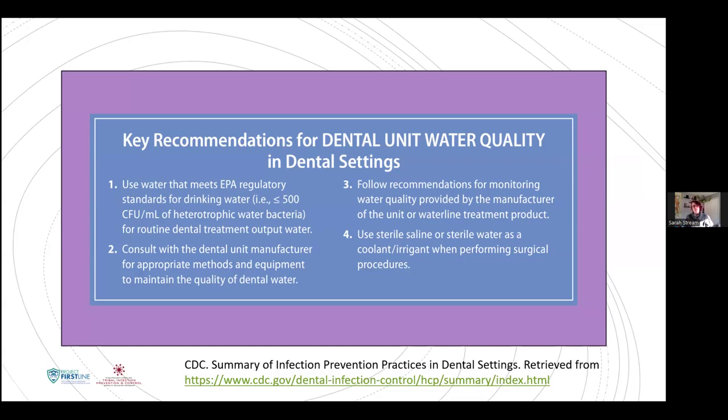And there is a lot of confusion in the dental community about what water do I use? Does it work with my dental unit? Am I using the right maintenance chemicals? Am I using the right shock chemicals? And it really all depends on the IFUs of everything you're using. Some require distilled water, some require filtered water, some require tap water. It just really is all very situational.